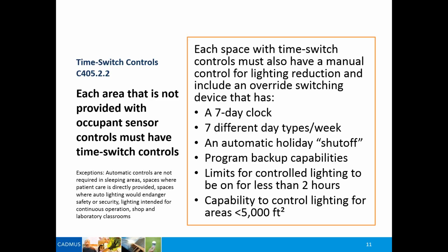So basically, you could put occupancy sensors through the entire building if you wanted to do that. But if you didn't want to do that, then it would have to be, again, on a scheduled basis, some kind of lighting control system that would automatically turn the lights off during non-occupied hours. And there's some criteria for that. So basically the same requirement as you have in the 2006, except again, you're going to be required to put in occupancy sensors in a lot of occupancy types, and where you don't have that, then you install an automatic time clock to be able to shut the lights off.